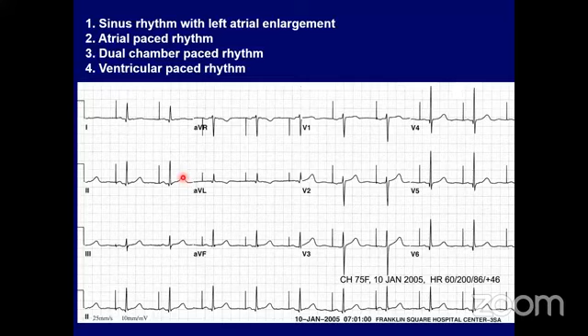Sir, most of the time, the pacing ECG we have, even with atrial pacing, they have very small spike, and most of the time you cannot actually see. But what you can see, there's a fixed rate sometimes. Yes. If you put the magnet in there, then you can find out actually. Yes. The older pacemakers with unipolar pacing would show spike better than a new pacemaker, bipolars. That's one. Secondly, the filtering mechanism in the ECG a lot of times eliminates. And there is another problem. There are newer machines which put spike when there is no spike. So I want on this one, please.